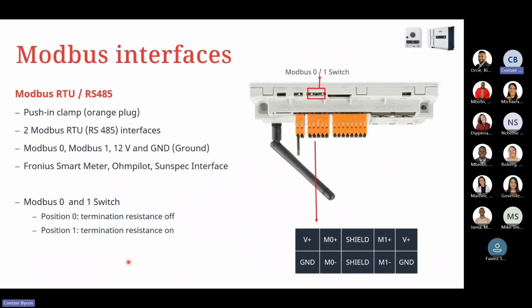So again, on the Modbus interfaces, you've got your Modbus RTU or RS485, which is a push-in connection plug, those 2 orange connector plugs that are available. The one is for your RS485. M0 is one of the protocols, and you've got M1 as the other protocol for your Modbus side. What you'll see is there's a simple switch located on the top of the pilot device itself. This allows us to turn on the 120 ohm terminator resistor for the unit itself. This is handy when we are adding a smart meter to the system. We will need to make sure that we have the terminator resistor either on or off, depending on which smart meter we are using. Some smart meters require that resistor to be turned on or off, and some don't.